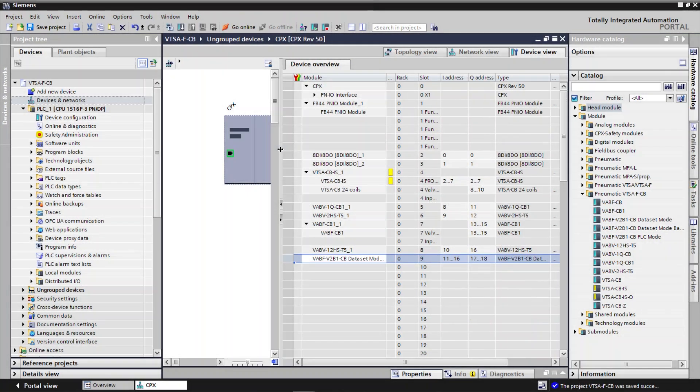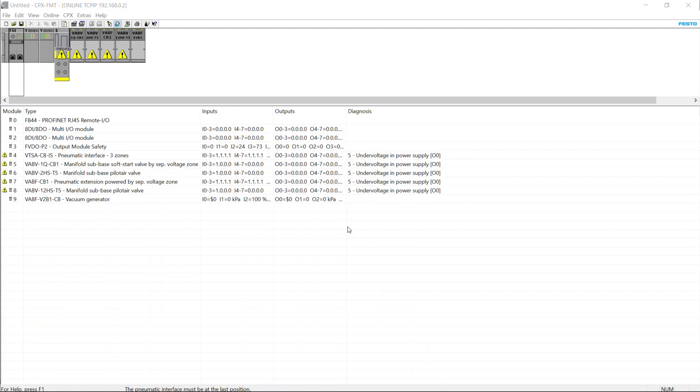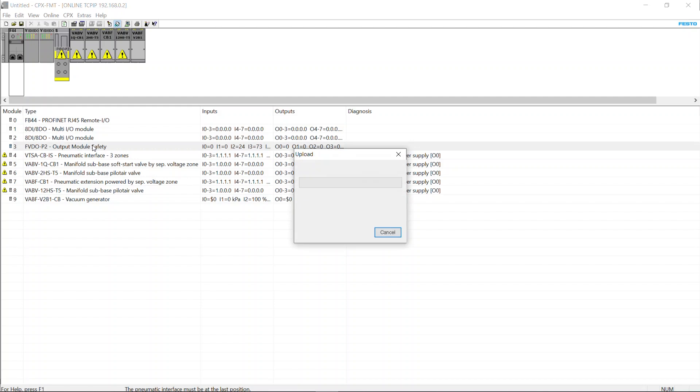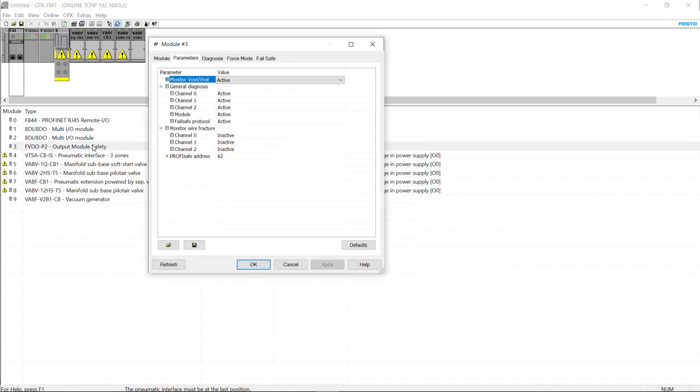Check the ProfiSafe Address using CPX Festo Maintenance Tool. Open CPX Festo Maintenance Tool. Double click on FVDO P2 Safety Output Module. Here you can see the ProfiSafe Address.